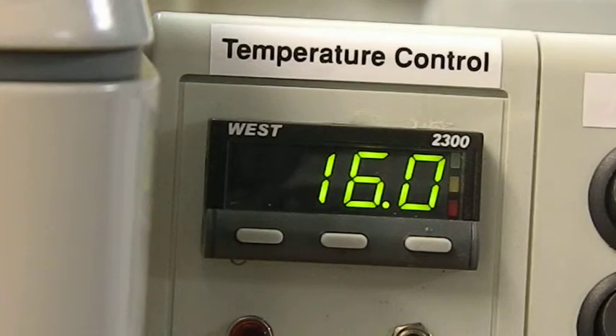It's very rare we have to make a second adjustment, but you can do that adjustment whenever you like. I would suggest you don't do it too often, because every time you change it, you're altering the whole background sort of registration for the controller. So it's best to do it perhaps at the beginning of the season at a low set point of perhaps 16 or 17 degrees, then again at 37.5 to be sure. And if you do find there's a differential between your mercury thermometer or your digital thermometer inside the machine at the top of the egg and what the controller is reading, then it's just as well to check that your calibration hasn't altered. It shouldn't alter.